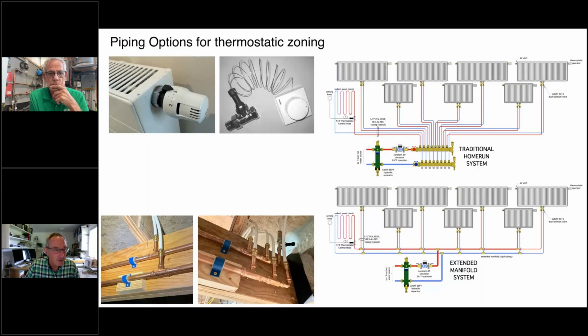I can't overemphasize that. And I say that because we've had projects where people have cut these with diagonal cutters and said, I'll just put it back together with a wire nut. That's actually a little tube, and the working fluid is moving through that tube between this little piston assembly here and this wall actuator. Over here, here's a manifold, variable speed, constant differential circulator.